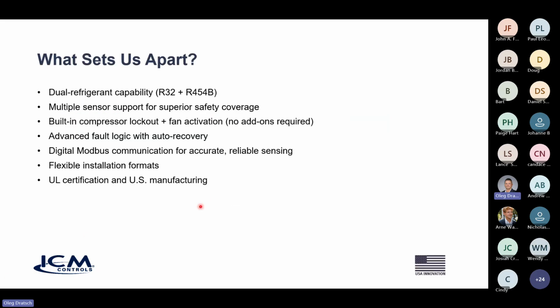So our refrigerant, I should mention, is dual refrigerant capable. So you'll see some sensors on the market that just sense R32, or some that just sense R454B. The ICM controls Universal A2L mitigation kit senses both. So you don't have to worry about carrying extra SKUs. You don't have to worry about which refrigerant you're sensing.